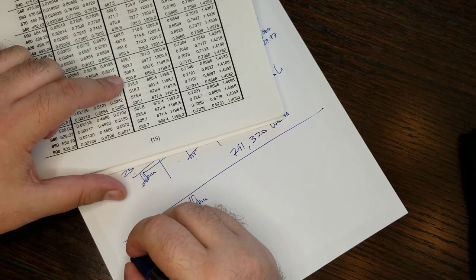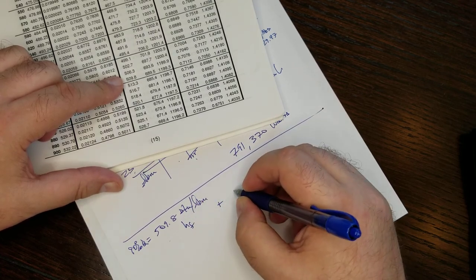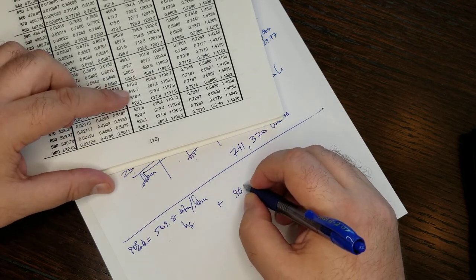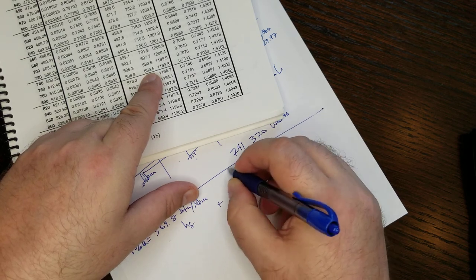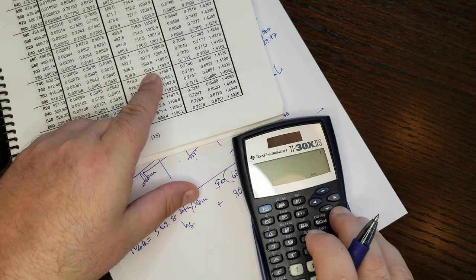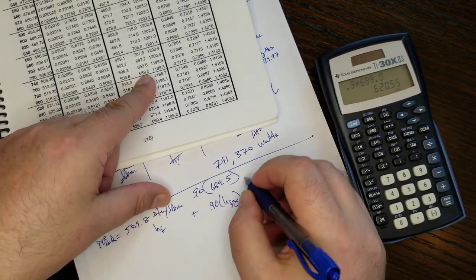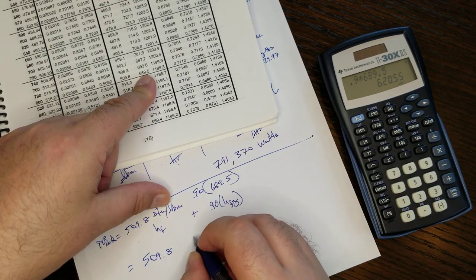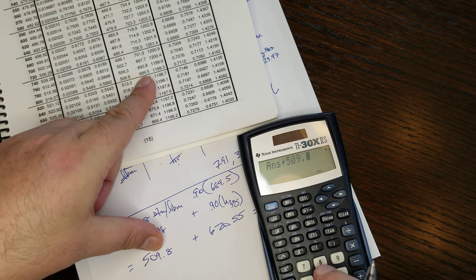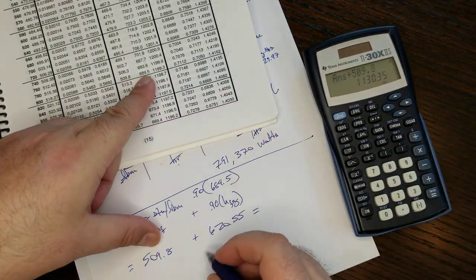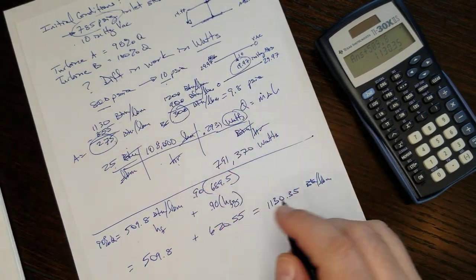So 800 PSIA has an H sub F of 509 BTUs per pound mass. But the actual enthalpy of 90% quality is that initial H sub F plus 90% times H sub FG. So 800 PSIA, 689.5, 90% of that is 0.9 times 689.5 equals 620.55. 509.8 plus 620.55 equals 1130.35 BTUs per pound mass.